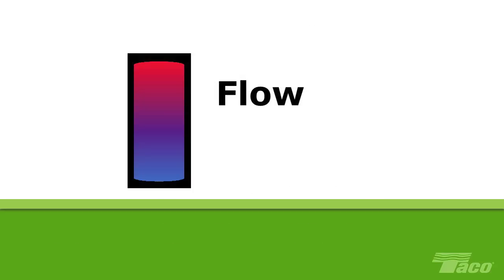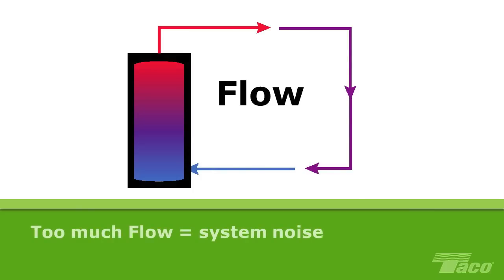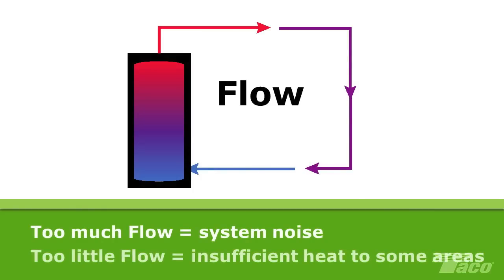Flow, measured in gallons per minute, is the rate at which water must be moved to carry heat throughout a hydronic system. Too much flow results in system noise. Too little flow means insufficient heat will reach at least some areas of the building.